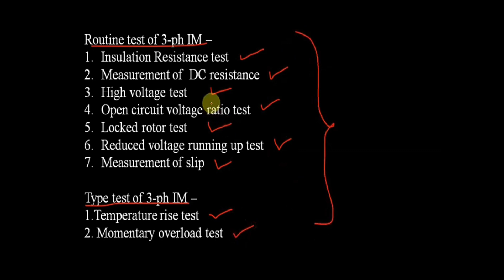So the routine test of 3-phase induction motor includes insulation resistance test, measurement of DC resistance, high voltage test, open circuit voltage ratio test, locked rotor test, reduced voltage running up test, and measurement of slip. These are all in the routine test of 3-phase induction motor. And next is type test of 3-phase induction motor. Type test includes temperature rise test and momentary overload test. So these are about the routine test and type test.